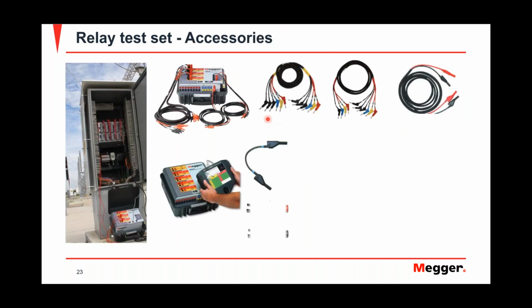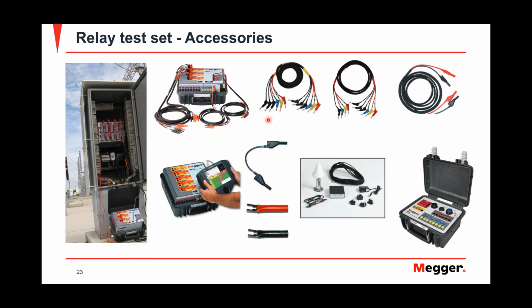Some accessories that you could have, make sure that you have the right accessories, enough cables. These are current cables, these are for voltages, these are for IO, having enough depending on the type of testing that you're doing. Having a dedicated controller. There are some nuclear sites where you're not allowed to bring a laptop or pull out information. Different test sets have dedicated controllers that you could use directly with the relay test set. That way, you don't need a laptop in there. You could just use the dedicated controller.